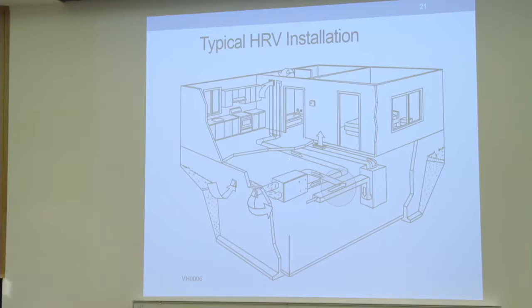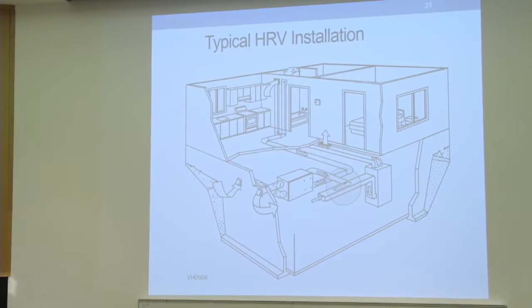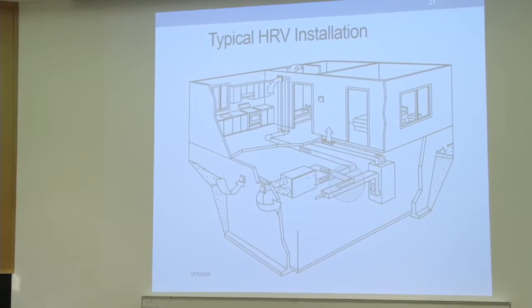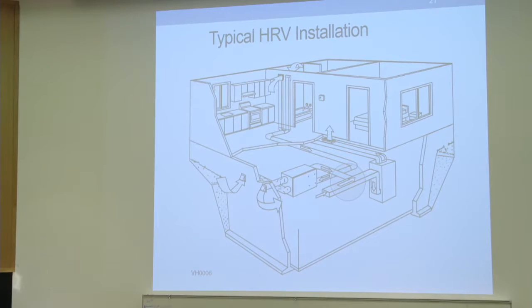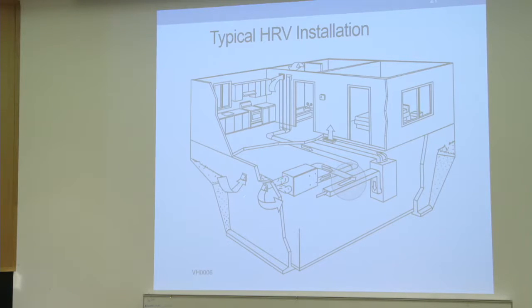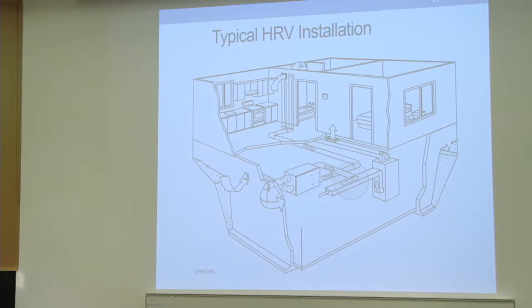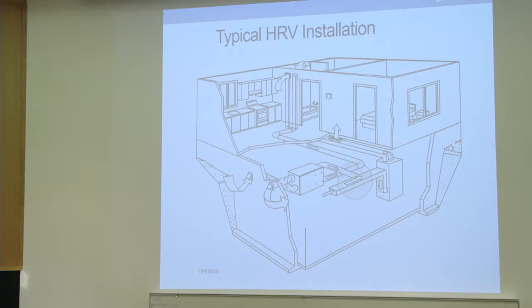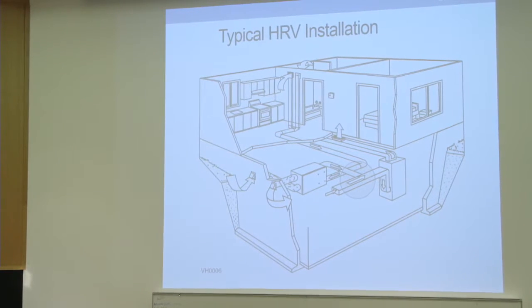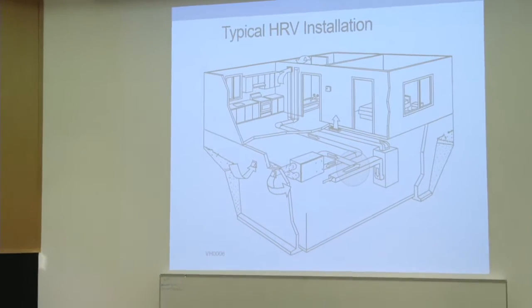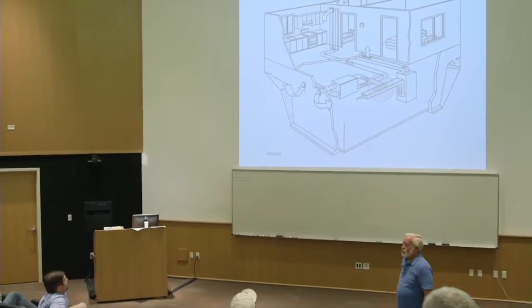Typical installation to do a ventilation system. Here's a 1-bedroom house. Here's a bedroom. Here's a bathroom. Here's a kitchen. You draw exhaust sidewall in the kitchen, draw it out of the bathroom, through the ventilator to outside, bring in some fresh air, and just dump it into this return so it just distributes it throughout the house. I put in these 25 years ago in some homes. I put them in my house that I built back then that I've since sold. It actually is a pretty slick system, but it's going to cost you some bucks.